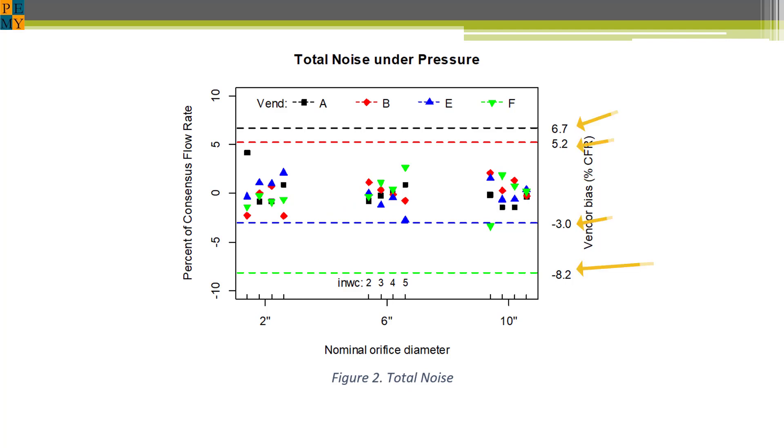Note how the vendor bias swamps the noise components, meaning that the vendors in their test rig are mostly responsible for the discrepant measurements. Vendor bias stands out above the noise, which is what it means to be statistically significant.